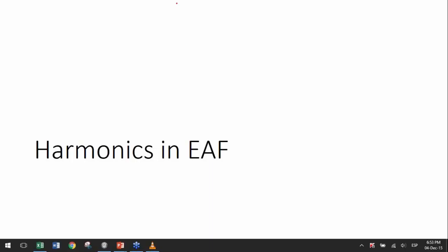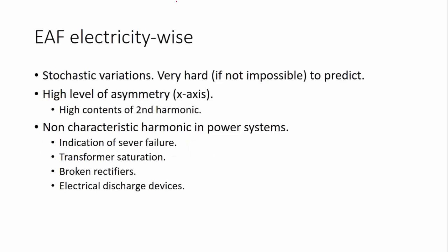Now, electrically speaking, the arc furnace is quite interesting because, as I told you before, it's a very stochastic, very random process in which you have no certainty on how the furnace will behave, how much current precisely it will draw, and especially what the harmonic spectrum will be. If you think of a motor, a drive, or pretty much anything, you can know with a fair amount of certainty how that machine will work power quality wise, and what the harmonic spectrum will be. In a furnace, you may have an idea, but it's very difficult, if not impossible, to estimate precisely. What is known is that it varies a lot, depending on what part of the melting process you're in.